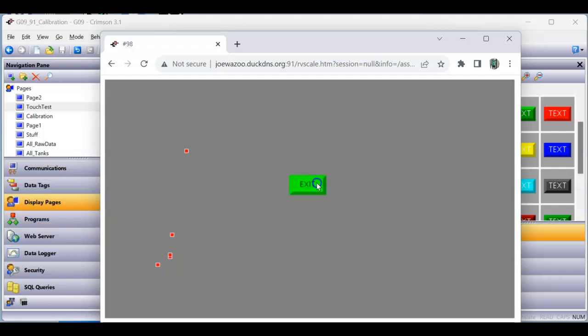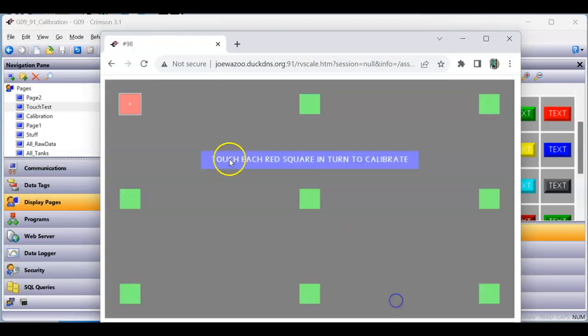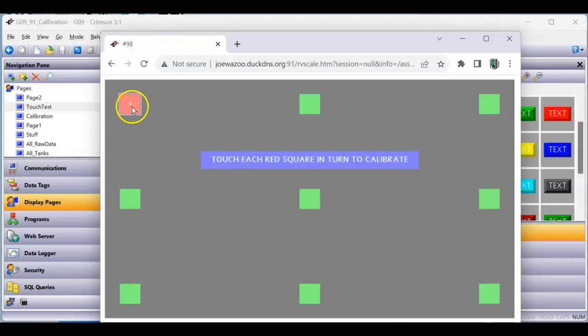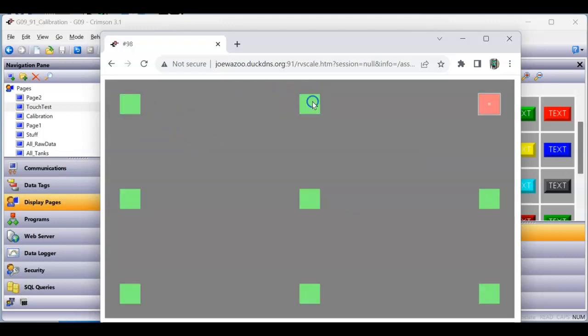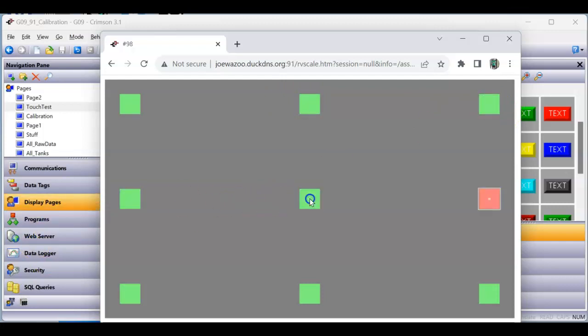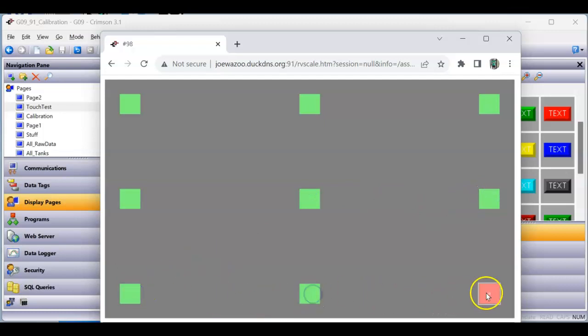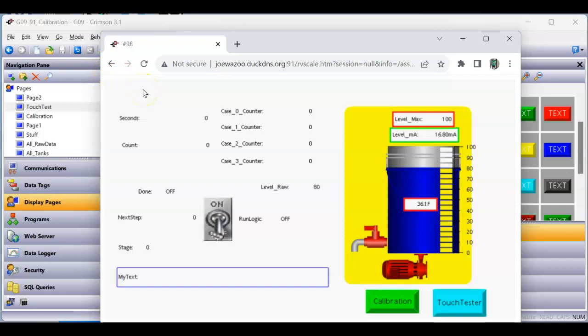If both tests still show calibration issues completely, you'll need to get with your distributor and do an RMA to send the product back to the factory. Those are two things you can do in your Crimson database: add a touch calibration page and a touch tester page to test things on your screen. Thanks a lot, folks — if you want a copy of this database, let me know and I'll send it to you. Have a great day!